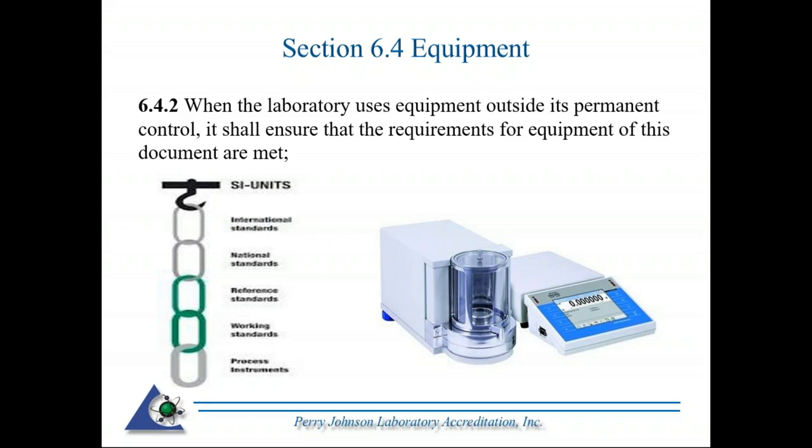I did an assessment some time ago where the facility was going to utilize this on a full-time basis, not just periodically use someone else's equipment to expand a range. Technically, they could do that. However, they also had to assure the traceability. Another thing that came to mind is the intermediate checks of that equipment. Just because the equipment was calibrated, and you might have a report, if it's going to be done on an ongoing basis, you want some sort of control to ensure that the integrity of that calibration is still intact.